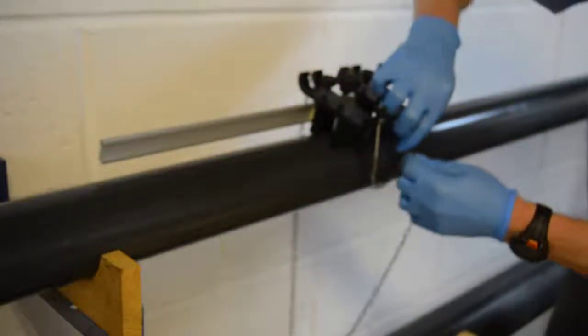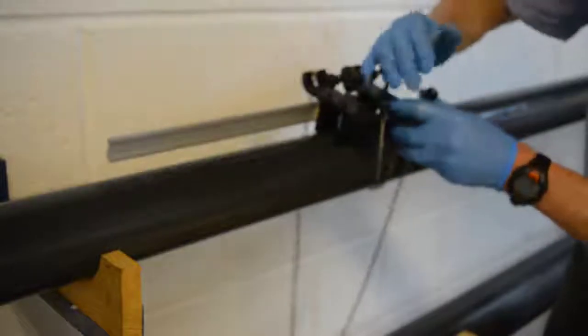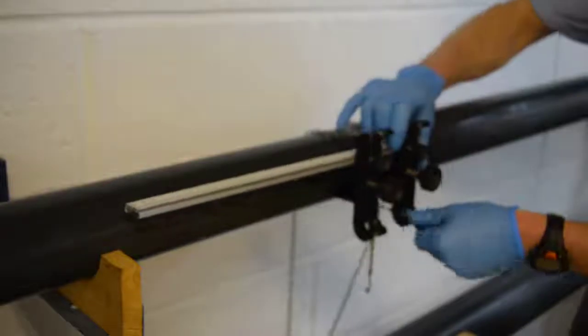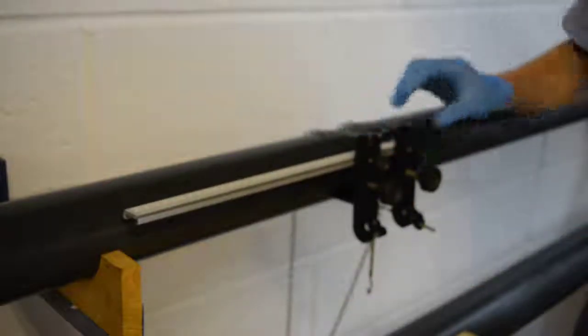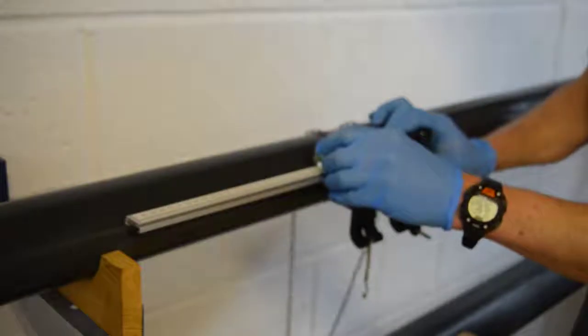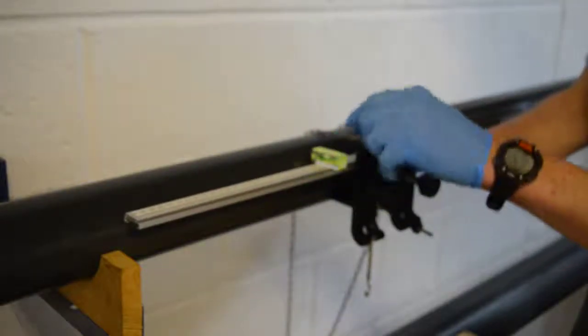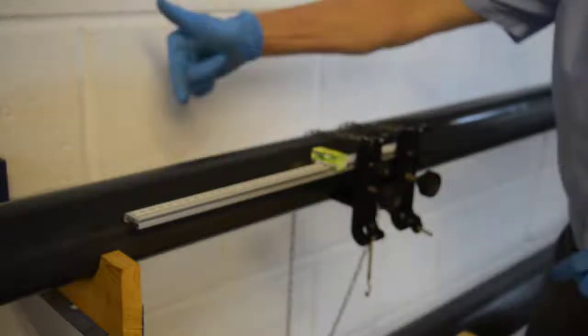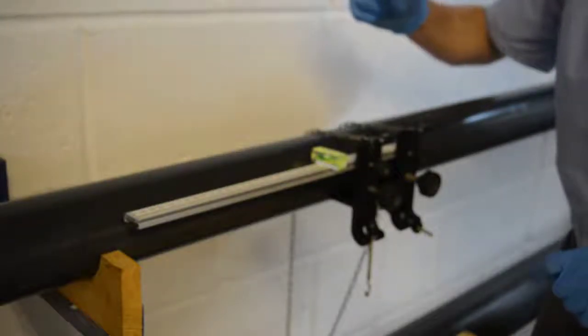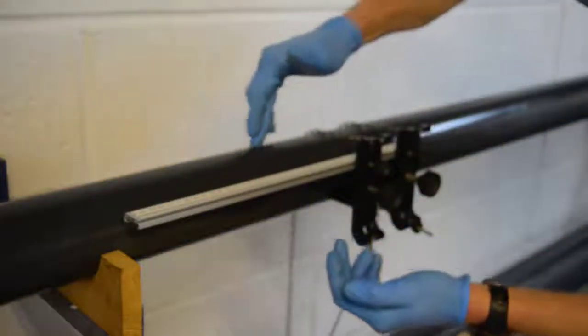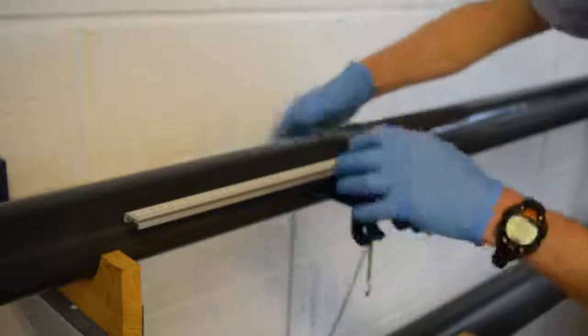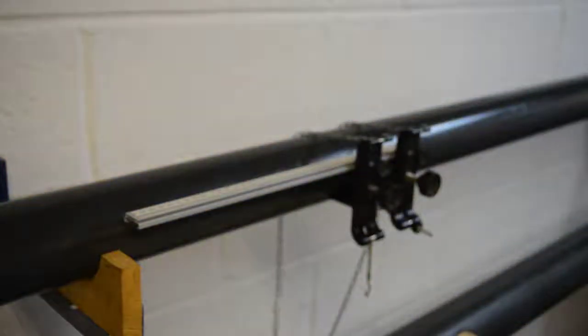And all we do is, now it's always better to have the sensors in a horizontal plane. This bubble level becomes important in Z mode when we're looking at the opposite sides of the pipe. So, but in you get air and debris here, so we always work horizontally if we can. Let's just check.